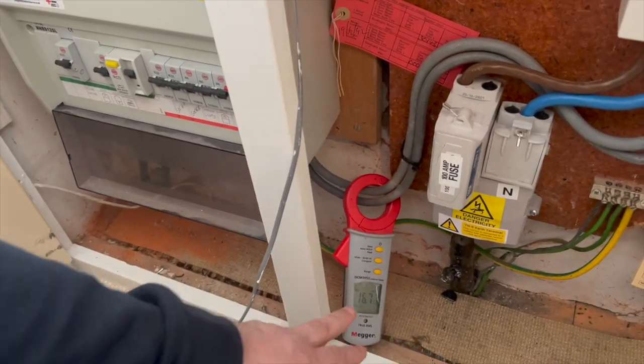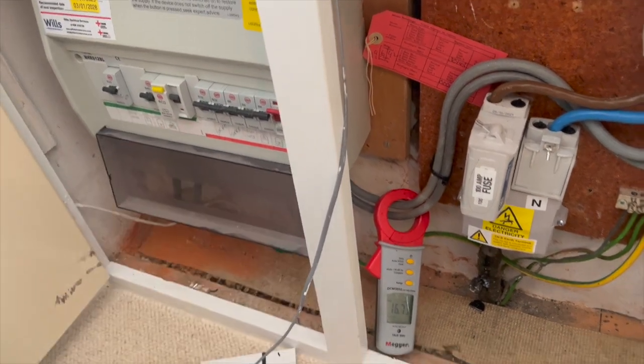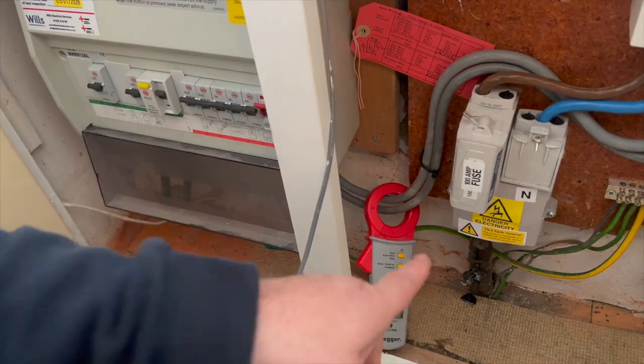Usually if you read over about 20 milliamps, then you might start tripping an RCD, because on a ramp check they usually come out about 20 milliamps. Well worth it.